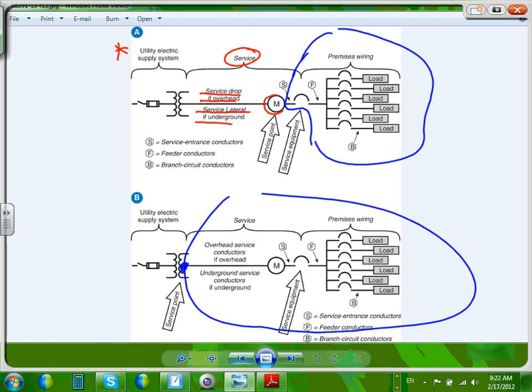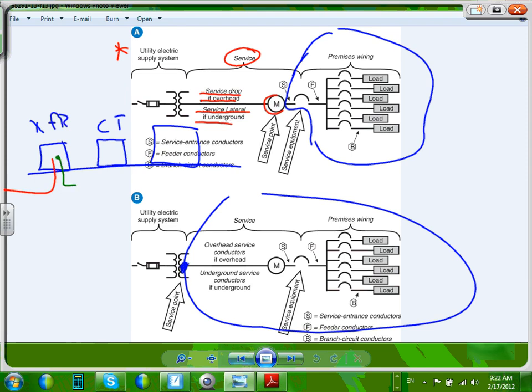Is there a rule of thumb guiding the position where you put your service point? Yes. Most of the time, your service point in a commercial building works like this. Let me just draw: here's my transformer, here's my CT cabinet, and here's my building, right? So most of the time you come to the transformer, and then out of the transformer you come with the CT cabinet up to here.